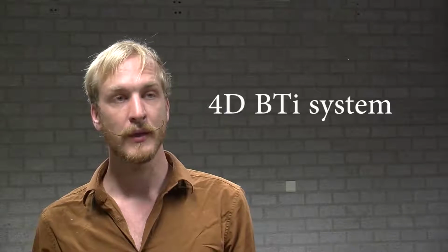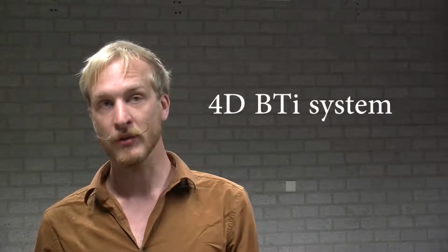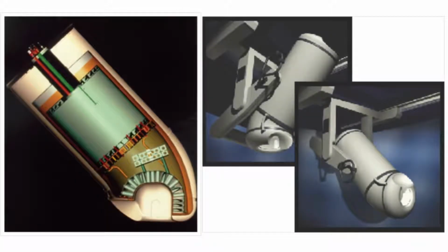Now finally, the last system I'll shortly discuss is the 4D BTI system. It uses magnetometers as well as reference sensors. And as we have seen, under relatively noise-free conditions, magnetometers are very sensitive to distant sources and can therefore pick up deeper brain activity than systems that use only gradiometers. But as you can appreciate by now, it really needs these reference sensors, and they are shown here in red.